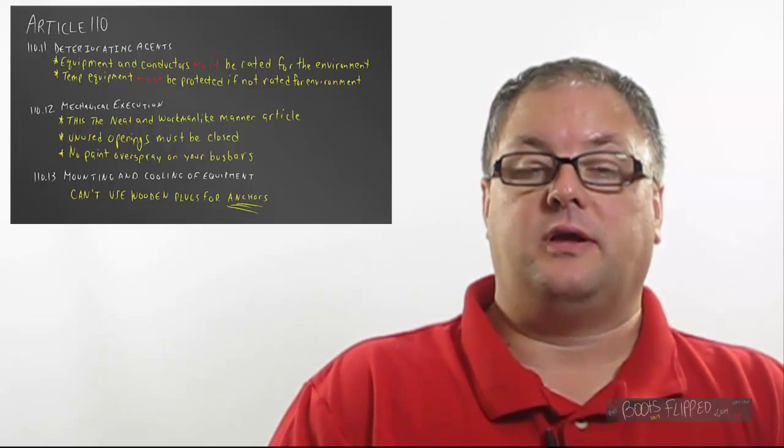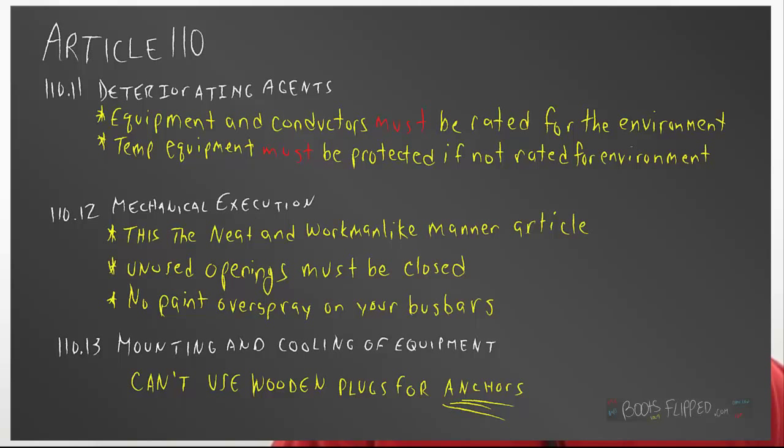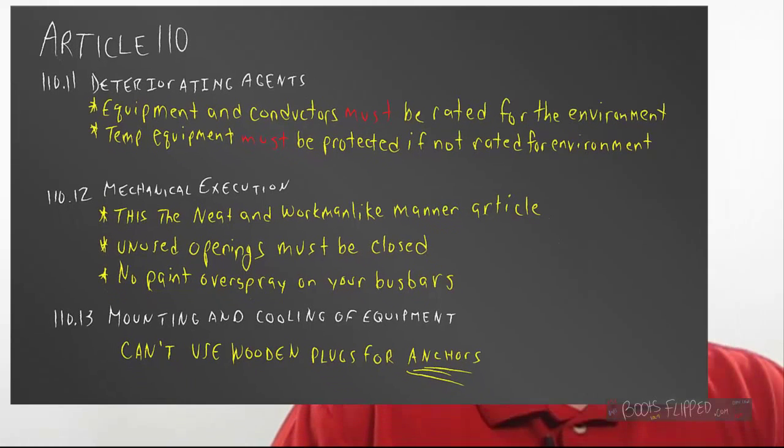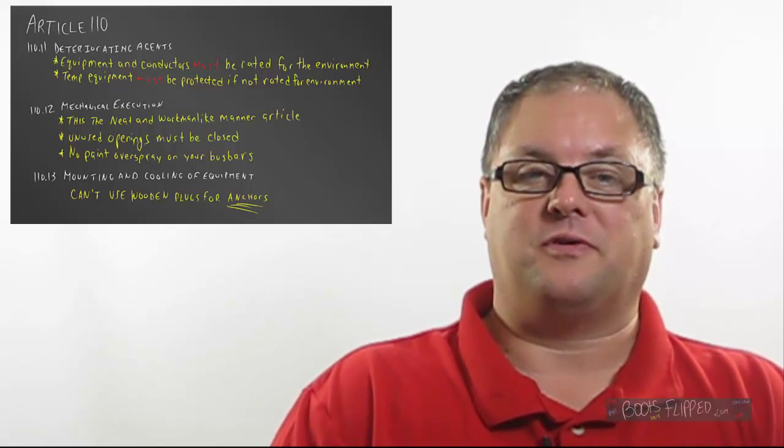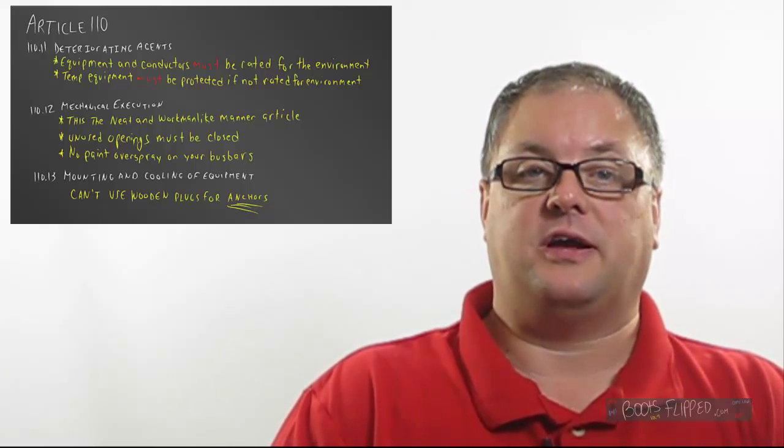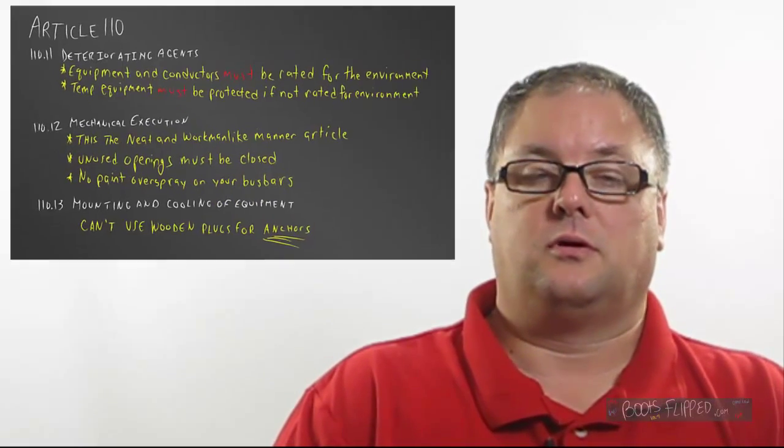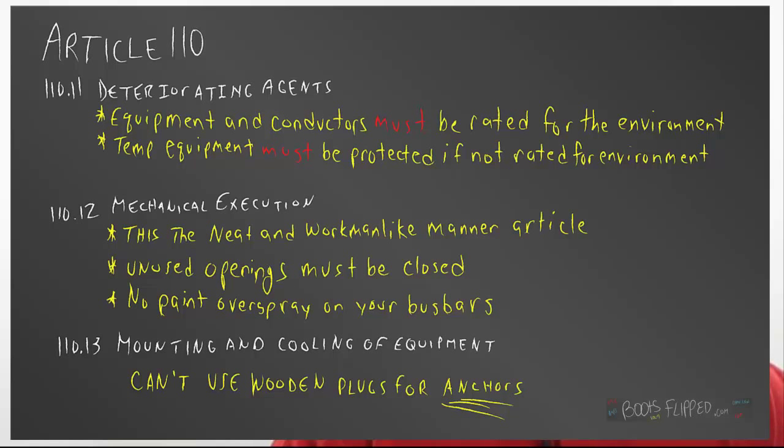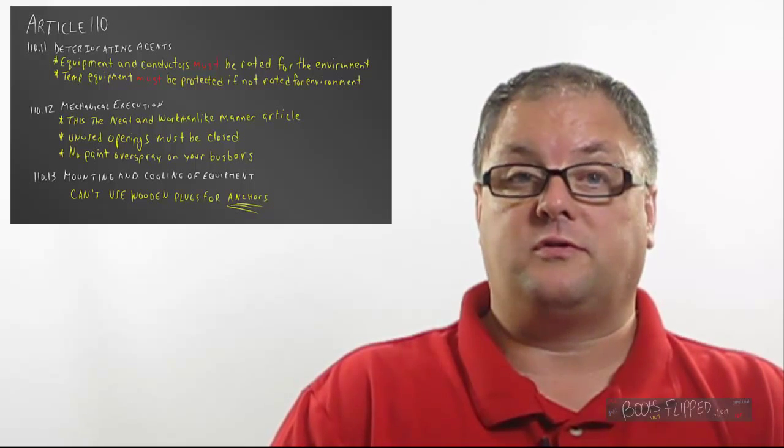Article 110.12 is an article that I believe one of you in class has already brought this up, but neat and workmanlike manner. Yeah, we have to make it look good. You know, your definition of good and my definition of good, I'm sure, are probably different. But it can't be a mess. And so an inspector could actually come into your job site and tell you that you've got to change it because he doesn't like the way it looks. Another thing that we have to do is we have to cover the unused openings. Yeah, that means if you're dealing with metal boxes and you take a knockout out, if you don't have another box to replace it, you have to use a knockout filler. By code, Article 110.12.